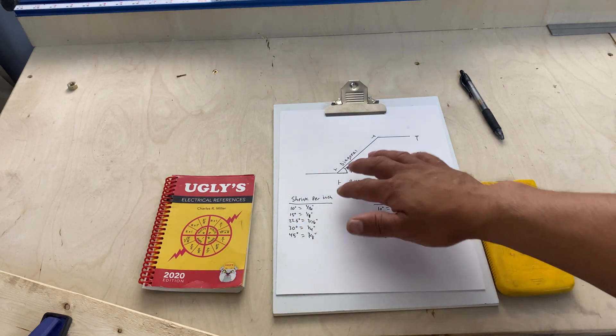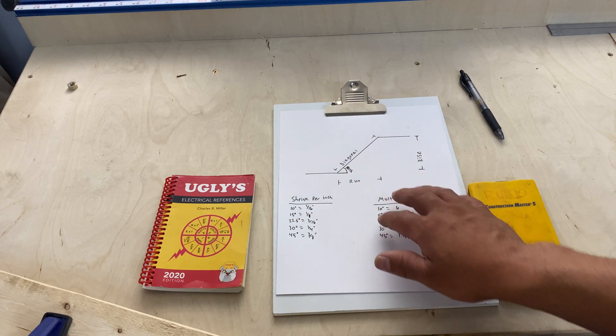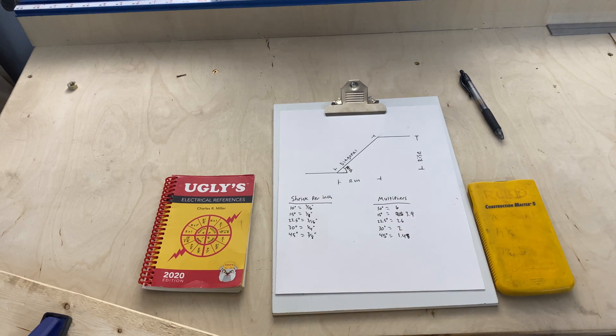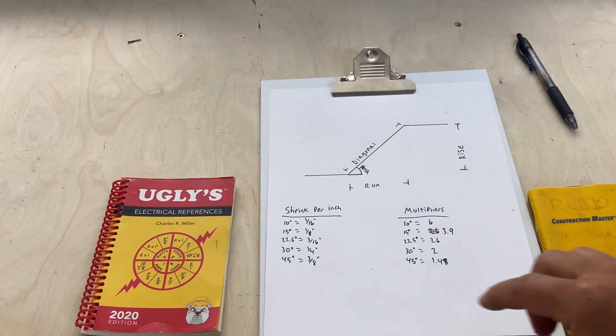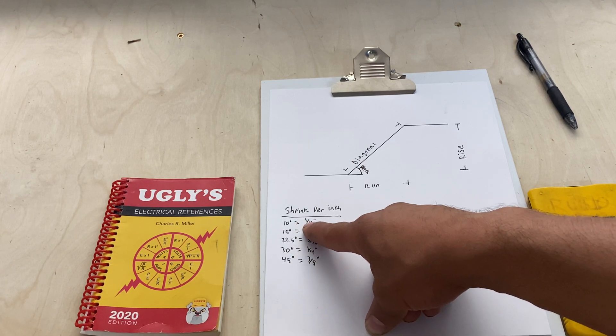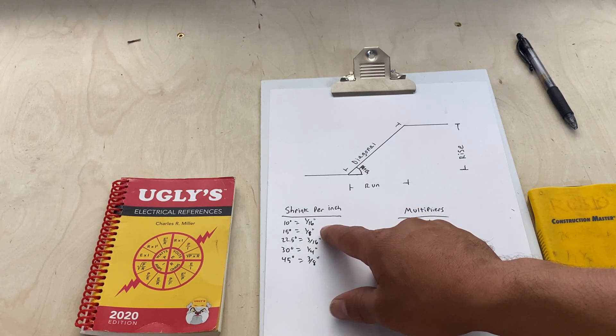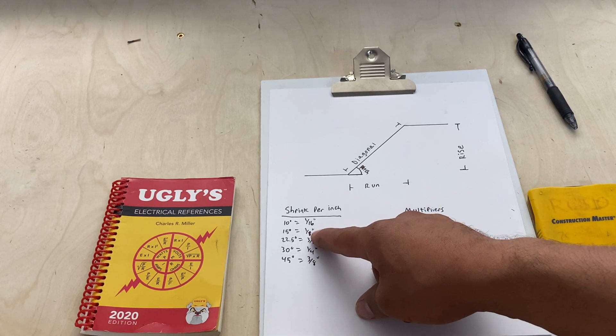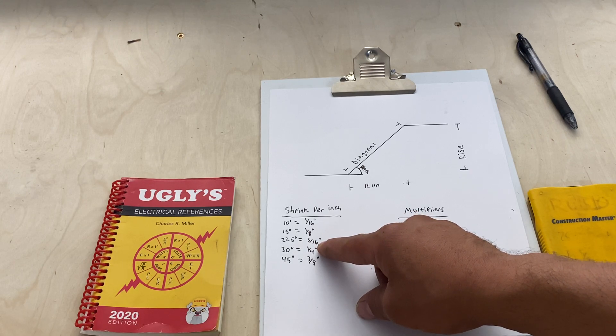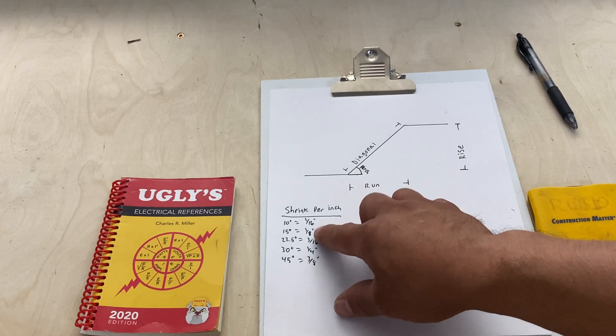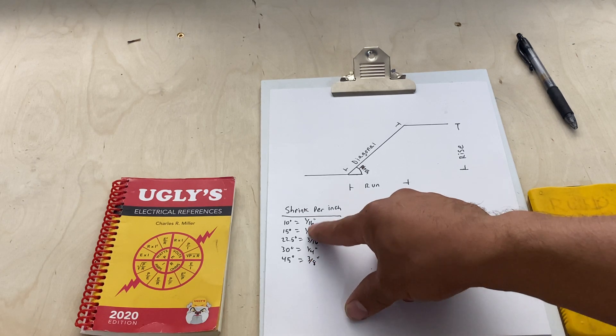Here I just drew a little diagram and put some descriptions on there with your shrinkage and your multipliers. Let me zoom in real quick. Down here on the left I have your shrinkage per inch. For every degree of bend it has different shrinks per inch. At 10 degrees you'll have a sixteenth inch per inch, 15 is an eighth of an inch, 22.5 is 3/16, 30 is a quarter, and 45 you have three-eighths. That's per inch, so if you're doing two inches you multiply these times two, three, four, five, and so on.